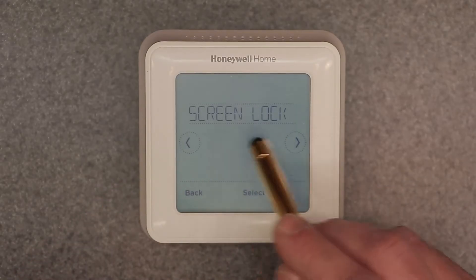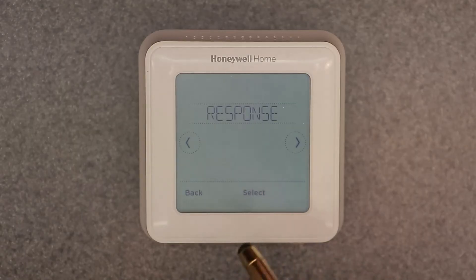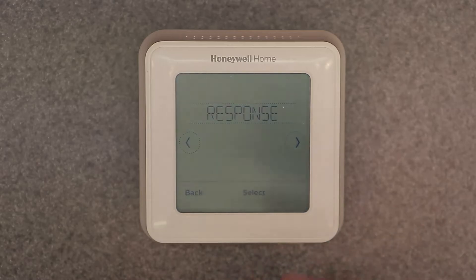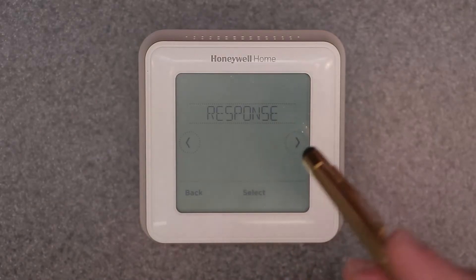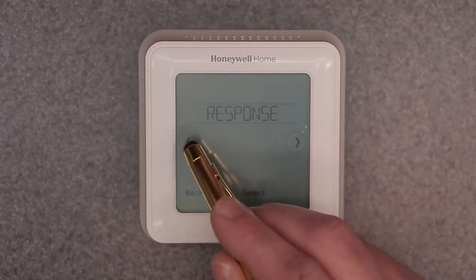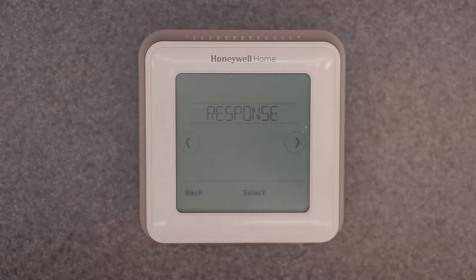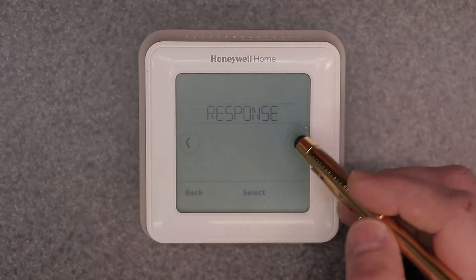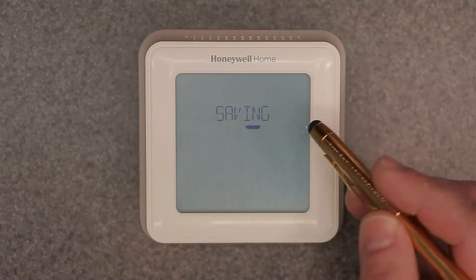Back in the main menu: screen lock lets you lock the screen with a password or PIN. Response is the smart response feature — the thermostat learns your patterns and will pre-start your furnace or air conditioning ahead of schedule. For example, if you want heat on at 7 AM, it might start at 6 AM to reach the set point by 7. I usually turn that off, but it's a useful feature. I'll leave it off and save.